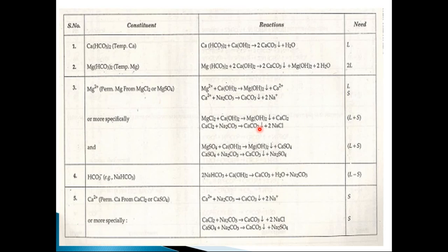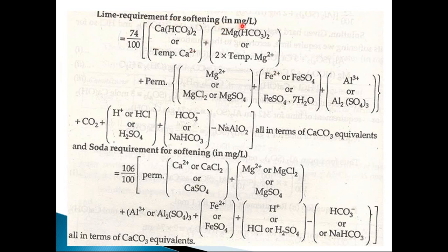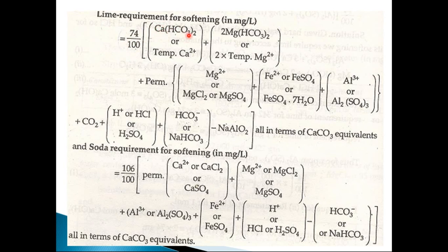Now comes the chemistry of the lime-soda process. The lime requirement formula for softening in milligrams per liter is: (74/100) × [temporary calcium hardness + 2 × temporary magnesium hardness + permanent magnesium hardness + free acidity + CO₂ + HCl + H₂SO₄ + iron + aluminum − sodium aluminate]. Here 74 is the molecular weight of calcium hydroxide (lime) and 100 is for calcium carbonate. In the formula, magnesium bicarbonate is multiplied by 2 but calcium bicarbonate is not — the answer comes from the chemical reactions.